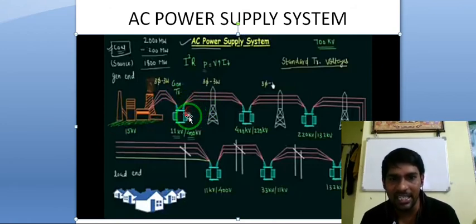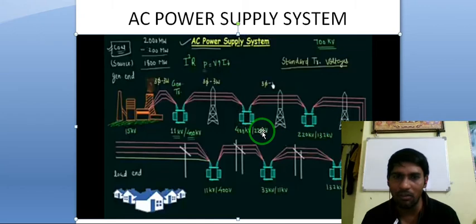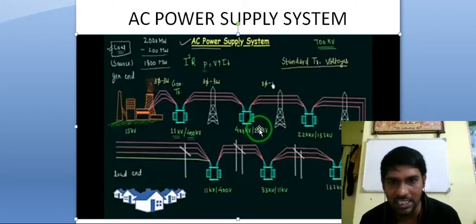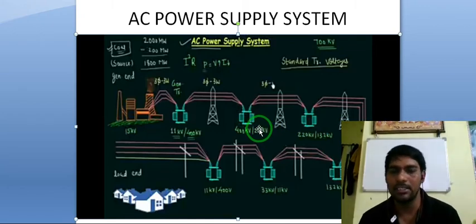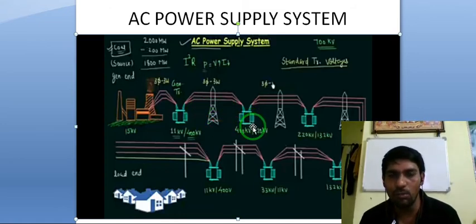In between the generating station and the load center, we are using different substations. The main components used in these intermediate substations are transformers. These transformers are called power transformers. The main function of the power transformer is to step up or step down the voltage levels. Here we are using one more substation. By this substation, we can step down the voltage level from 400 kV to 220 kV.